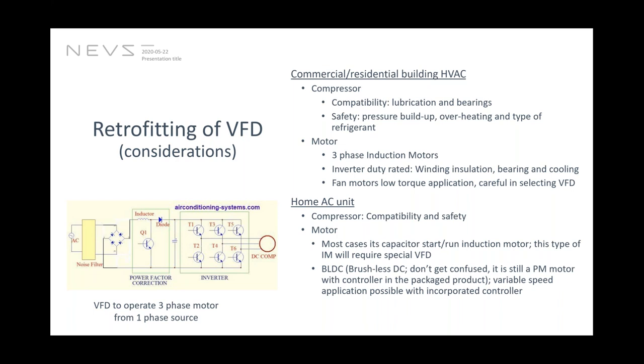So anyway, these are the commercial building at work, and the home AC unit is a different beast in itself. Usually in the commercial AC unit, either due to the propriety of the product or something, the compressors are sealed shut. And the motor is incorporated into the same hermetically sealed unit, so it is quite difficult to swap the motor in the compressors.